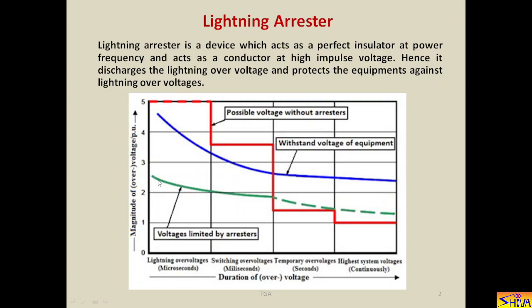So at this point the lightning arrestor is sparking. So the lightning over voltage is coming. In the absence of a lightning arrestor, it will go up to this value and it will cross the BIL of the equipment being protected, and it will damage the insulation of the equipment. So at this point the lightning arrestor is sparking and it is providing a path of low impedance to this lightning over voltage and it is discharging the lightning over voltage. So in this way it is protecting the electrical equipments.